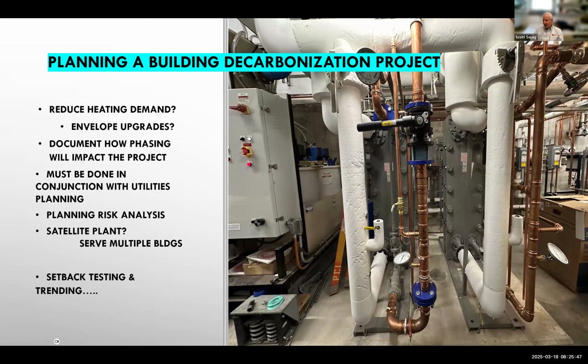We've done this on multiple sites and saved on secondary distribution piping costs, and which are the lower temperature and pressures, and lets us get off of the EN 253 steel piping. We use polyethylene piping between buildings. It's a fraction of the cost. Savings includes space and equipment and controls and piping.